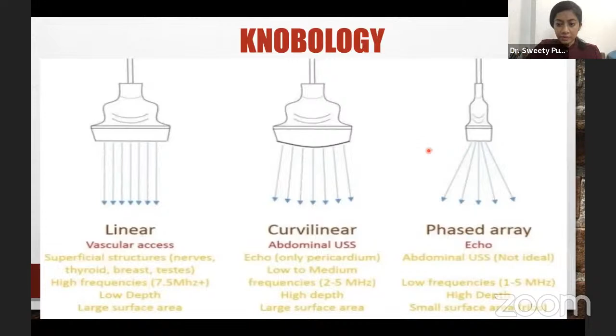And if you see the frequency, most often this is between 4 to 13 megahertz, and this one is lesser megahertz because it's a lower frequency. And this one is used for tight structures or small surface areas like ribs. There's also one more probe that we don't use unless required, that is the hockey stick or J-shaped probe. It is used for pediatric or finer structures. It also is a high frequency probe.